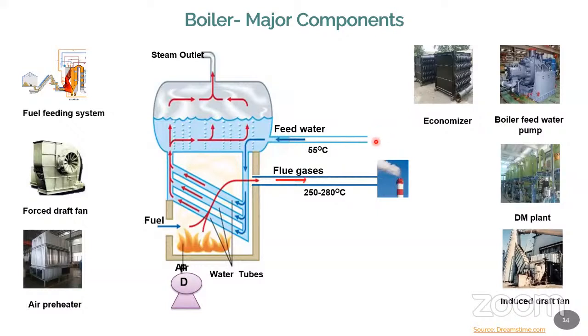Now, what is its advantage? Yes, it is a very, very huge advantage. Why? Because earlier you were increasing your water temperature from 35 degrees to 100 degrees. Now your inlet water itself is at 55 or 60 degrees. So you require less fuel. Less fuel is required to heat up the water because it is already heated up. So this is a very, very important, essential energy saving measure for the boiler. So condensate water, 100% to be returned to the feed water tank.